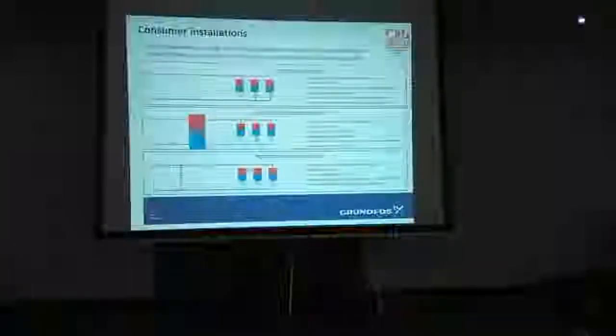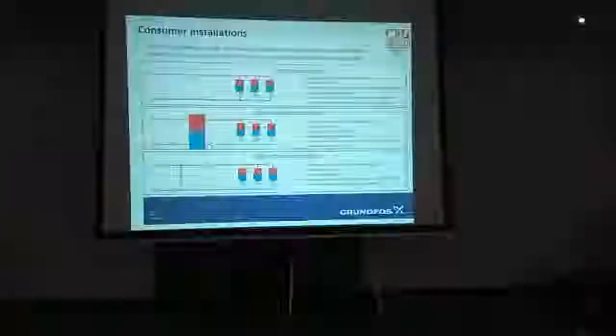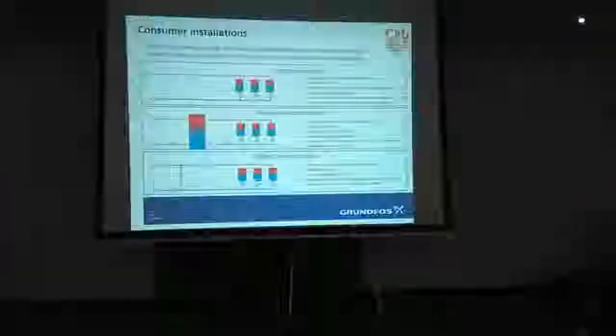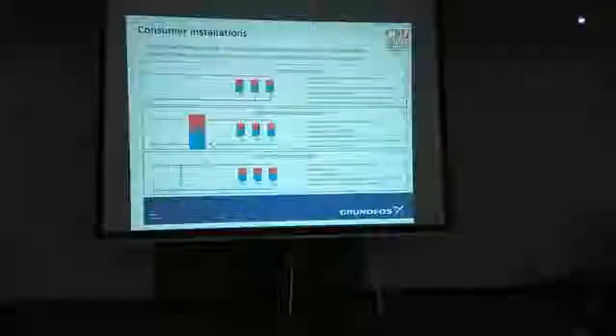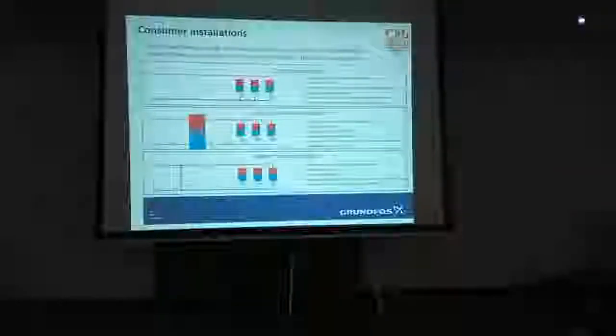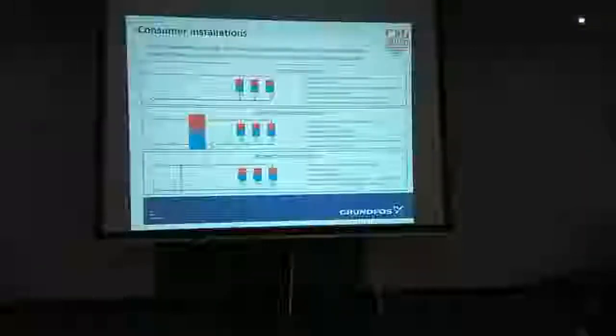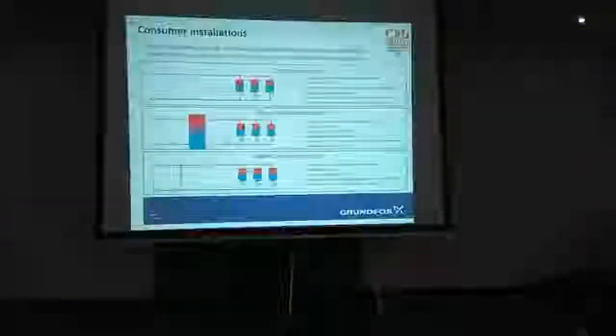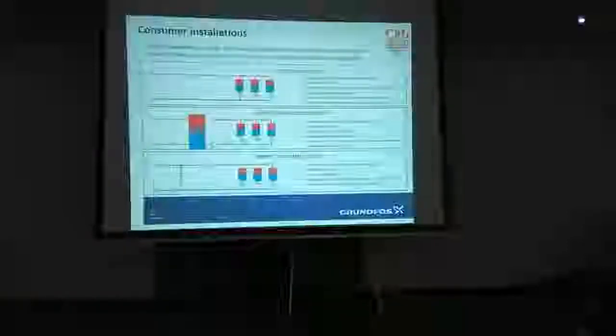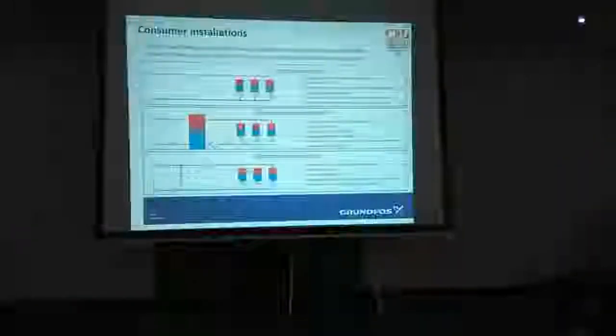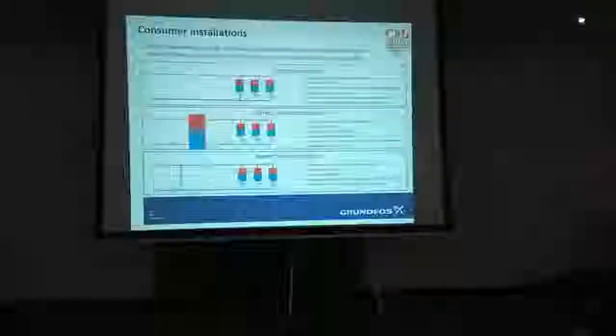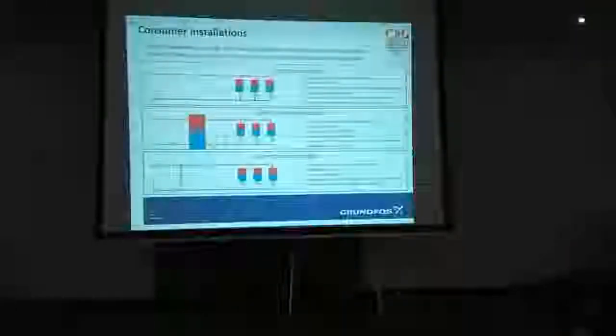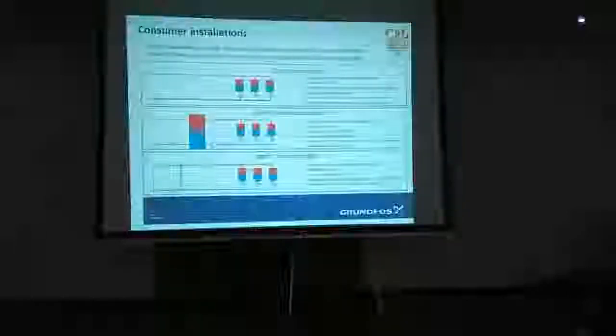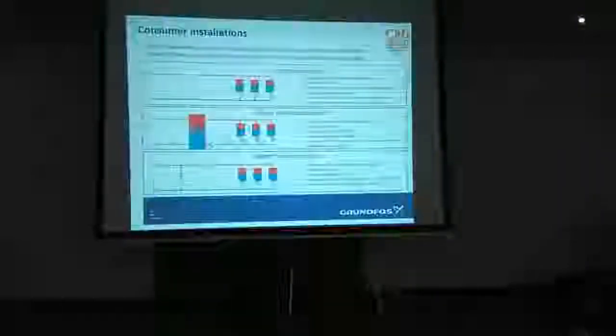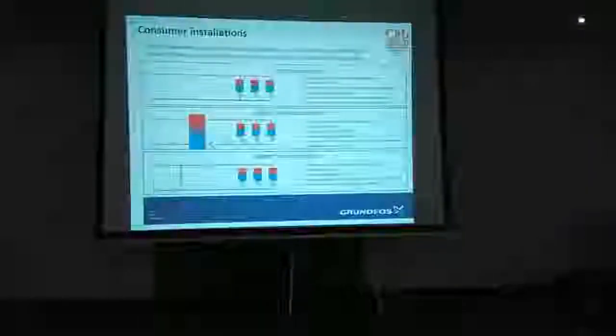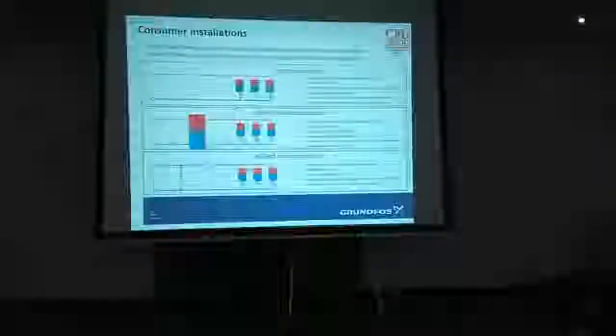It does work. And of course, if you've got a lower temperature here and you want a higher temperature here, this is where you can put your additional boilers or CHP or whatever into your own little bit. And you said you can chuck in 80 degrees C, but an industry factory might want 120 degrees C or whatever. You can add to it. But the core heat comes from the district. So a lot more flexibility with this one. Yes, it's more money. In the long term, it's cheaper to run, more controllable, energy savings are much easier to do. Okay? It's the long term that district energy is about, district heating schemes or systems coming into their own.